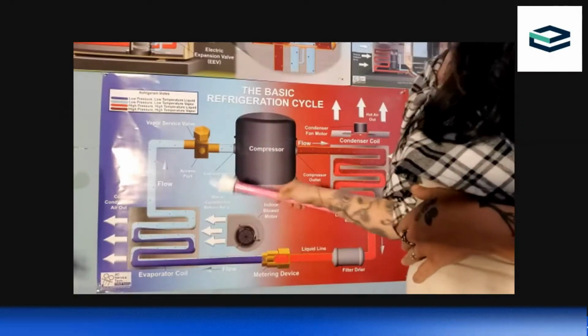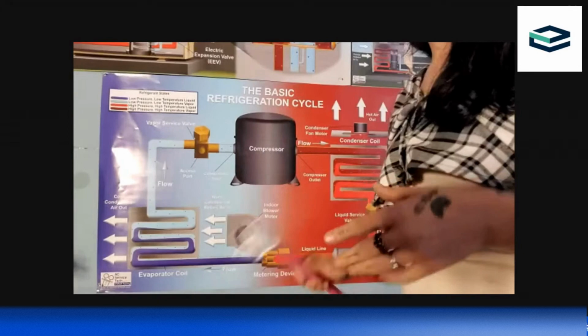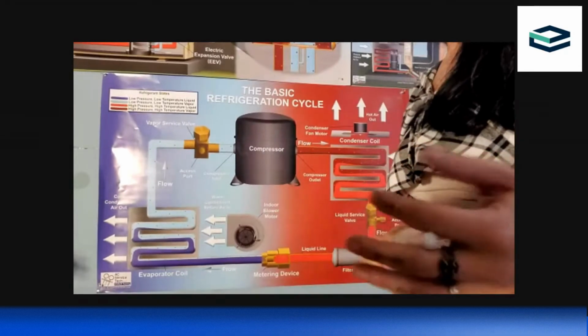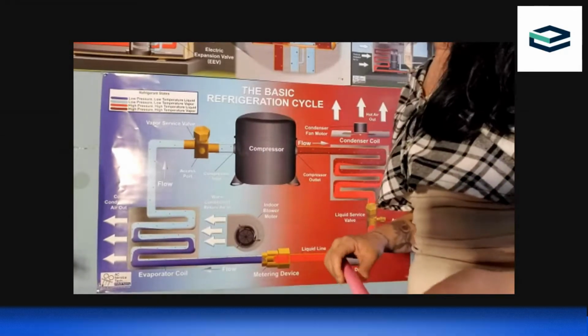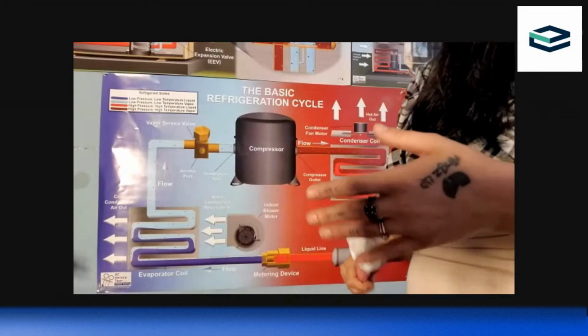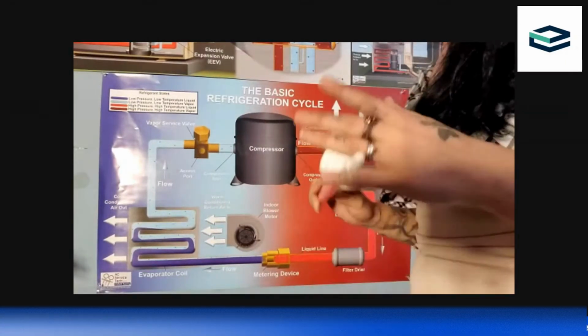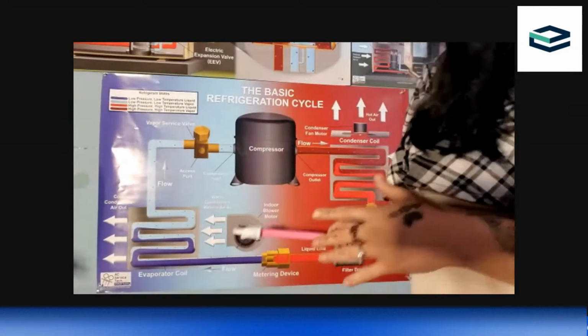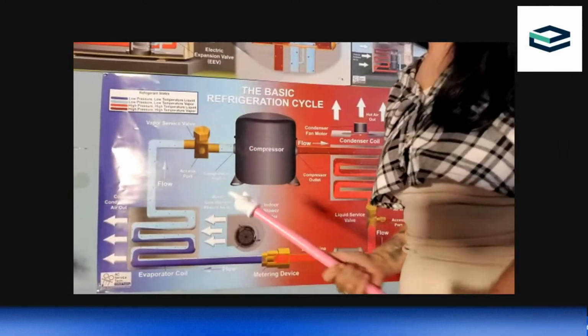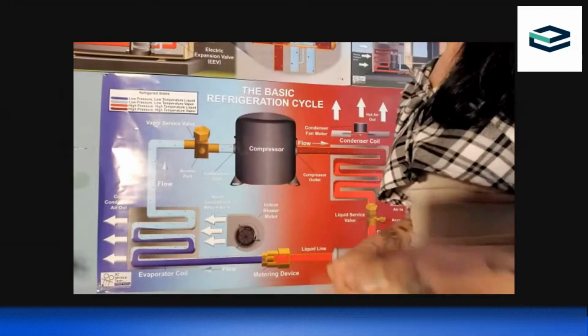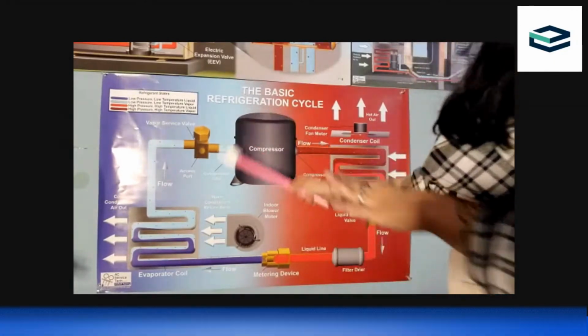This typically happens, liquid floodback is what we call it, and that happens typically if there's either a really bad restriction on one side for a very long time, or if it is overcharged. And if you overcharge a system, you can cause liquid floodback immediately, or it can take time. So it's very, very important not to overcharge a system.